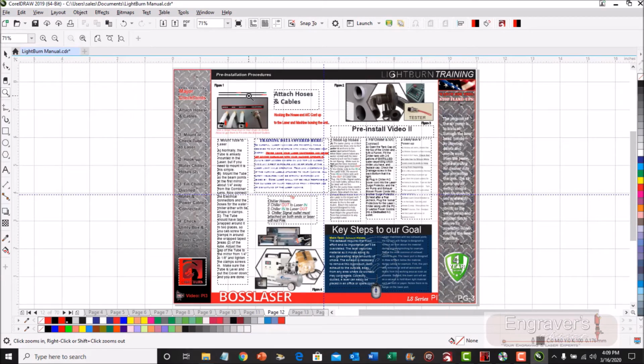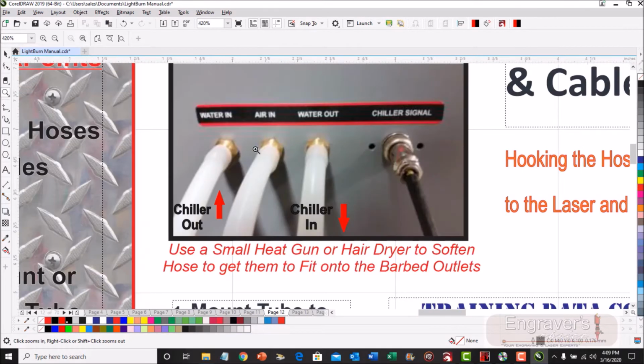now what you're going to see is the back of the laser, and you're going to see air hookups. And they may not be in this configuration. All you're looking for is water in, water out. The out of the chiller goes to the in of the laser. The in of the chiller goes to the out of the laser. This way you create a loop or a series circuit. You also have a signal cable that goes from the chiller to the back of the laser. Like I say, it may not be in this configuration. This is just one of many, many configurations.